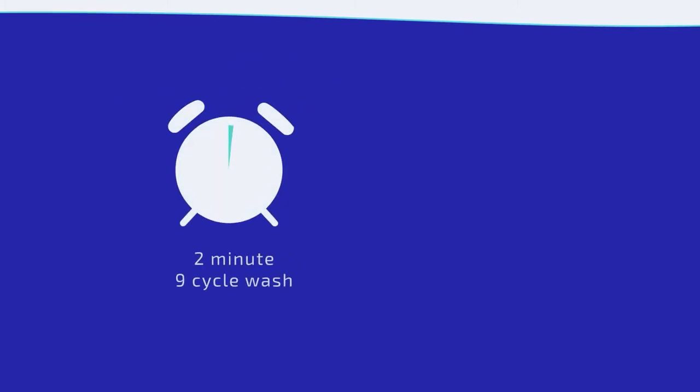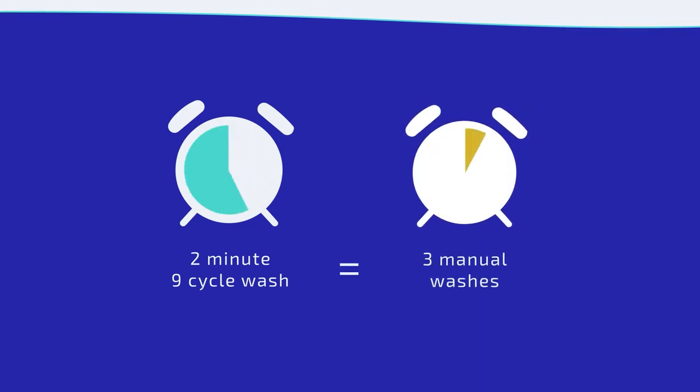A 9-cycle wash of 2-minute duration by laminar wash system shows washing efficiency the same as 3 washes using a centrifuge.